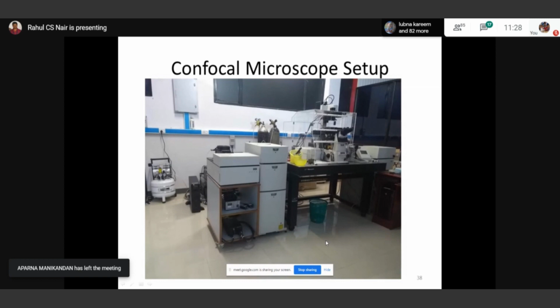transparent sheet-like material, which is called the incubator. And the incubator is needed because during live cell imaging, you need to mimic the living atmosphere, your body conditions. Suppose you are scanning human cells, you need to mimic 37 degrees centigrade with 5% CO2, because your respiratory system already maintains oxygen. So we cannot keep it open, and we need to maintain the CO2 level also. So 37 degrees and 5% CO2 condition we maintain in this chamber for live cell imaging, and overnight imaging is possible with this. And you can see gas cylinders, which supply the proper gases for maintaining the environment.